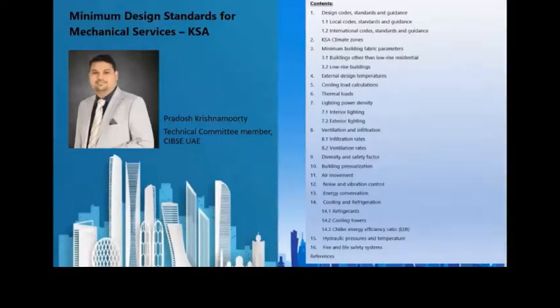For fire and life safety systems, there is no clear guidance on what particular life safety systems are to be employed. Therefore, the designer is encouraged to reach out to the respective fire and life safety designers to propose the system suitable for it. In general, the code covers the requirements for stair pressurization, lift shaft pressurization, and also for atrium smoke vent. There is no reference to, for example, corridor pressurization system that we have in UAE. That has not been specifically cross-referred in the SBC code. Therefore, for the fire and life safety systems, the guidelines recommend that they need to reach out to the fire and life safety specialist to propose the appropriate systems for the building design.